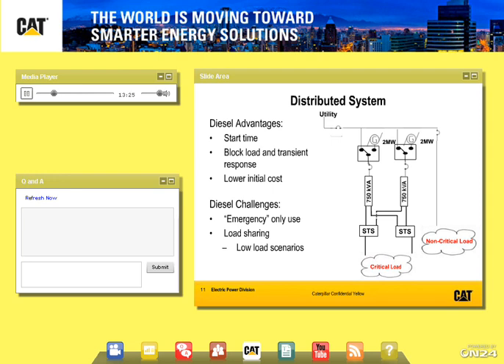I wanted to start by saying that in this example, I'm talking natural gas and diesel generator sets, and diesel generator sets are the clear choice for use in distributed systems. If the UPS system has seconds of ride through instead of minutes, which can be typical for this design, since you do not have to have time to parallel, you can have 10 to 25 seconds of ride through to get onto your generator set. In that event, you require the diesel generator set with the fast starting and the ability to pick up larger amounts of load in that short amount of time.